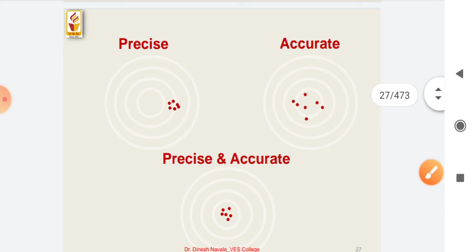In this diagram we can see the clear differentiation between precision and accuracy. In order to get precise and accurate results, we have to use a proper experimental procedure, and we need to eliminate the personal or user error and the calibration error. The instrumental error can be eliminated by using standard conditions for calibration, and if we do the proper calibration, then the results obtained are also accurate. So that is precision and accuracy.